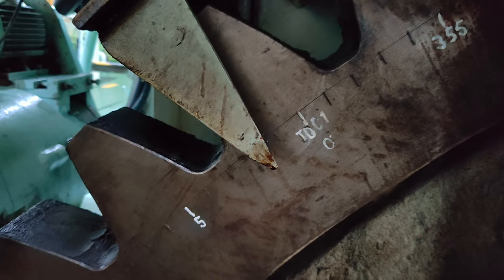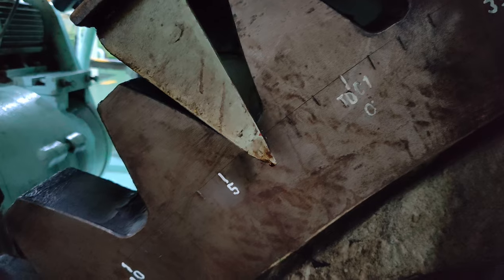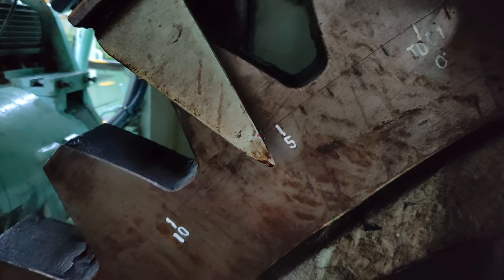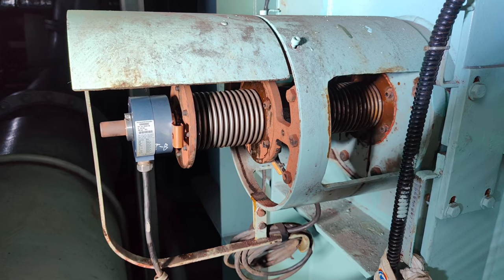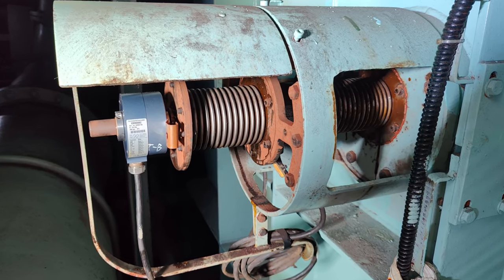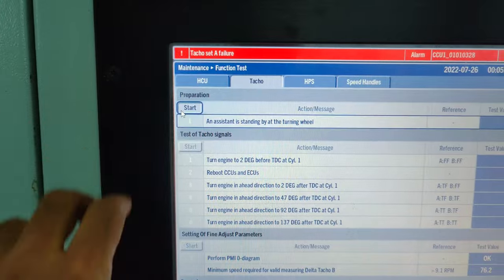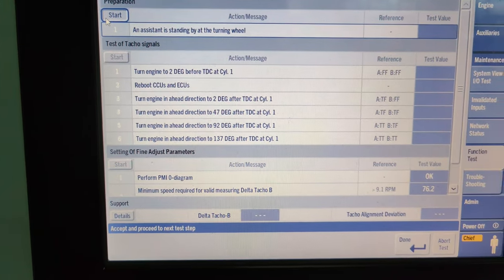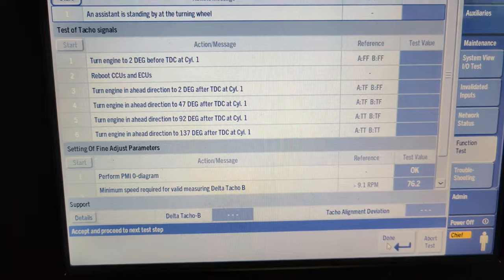In order to achieve the correct engine timing, it is very important to communicate an accurate position of the crankshaft to the engine control systems, and the same is being done by the angle encoders. As mentioned earlier, after performing the angle encoder alignment job, you need to conduct the MOP Tacho signal function test.